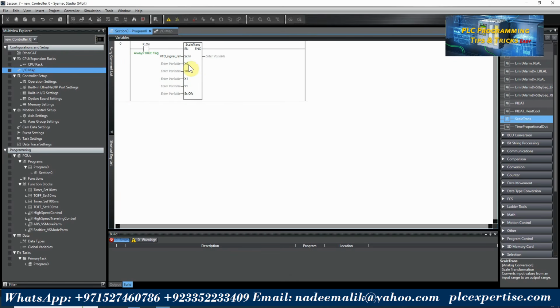Next, X0 is the minimum frequency we want to generate. X0 is the minimum speed reference. We can create here a variable with name VFD minimum reference. Data type will be real. X1 is the VFD max reference. Y0 and Y1 are the minimum and the maximum values which we are going to send to the analog output.